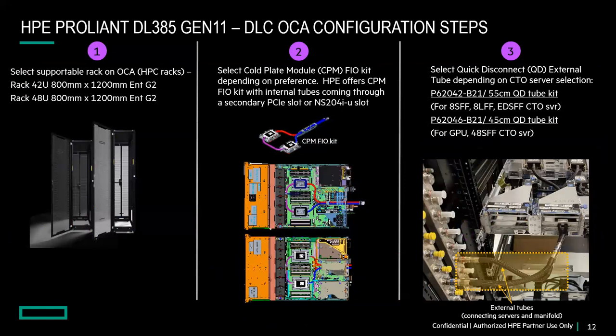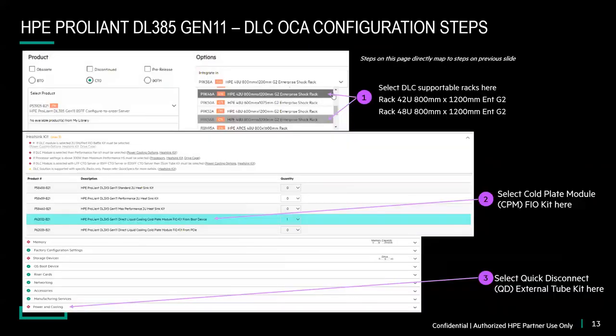In addition to selecting the cold plate and quick-disconnect kit, you also need the correct rack for direct liquid cooling — specifically the Enterprise G2 racks with an 800mm × 1200mm footprint, as opposed to the older standard 600mm × 1075mm. The extra depth and width provide room to route the pipes. In OCA, you can find the liquid cooling components under Processor → Heatsink Kit and under Power and Cooling.